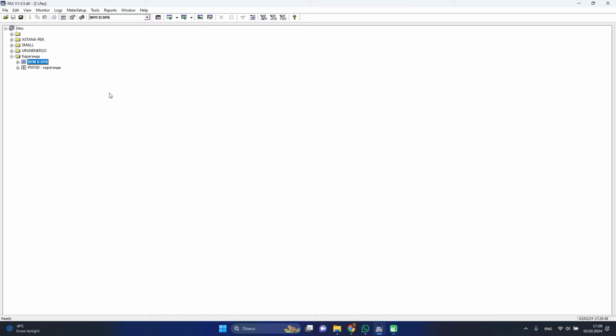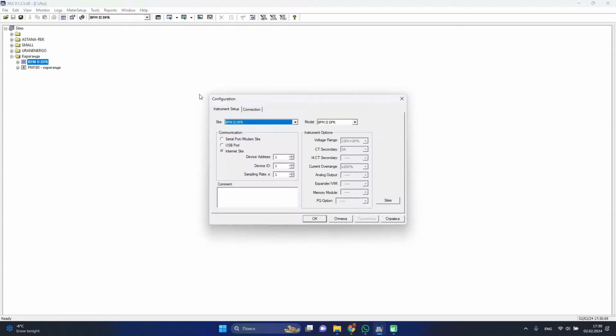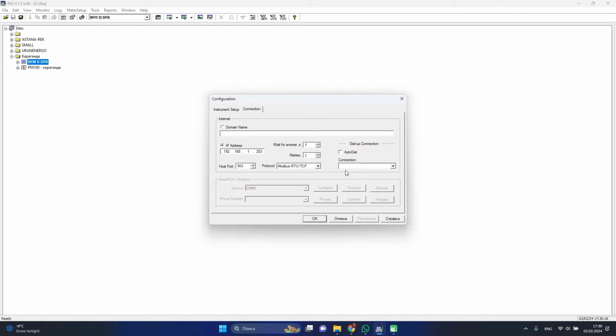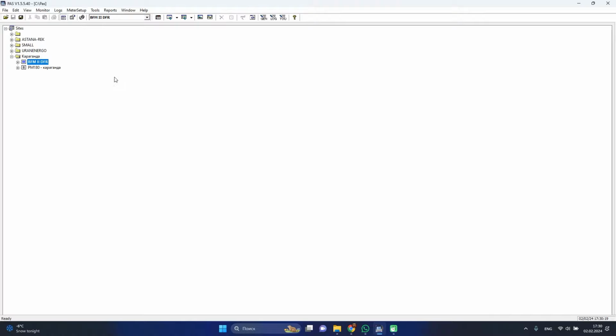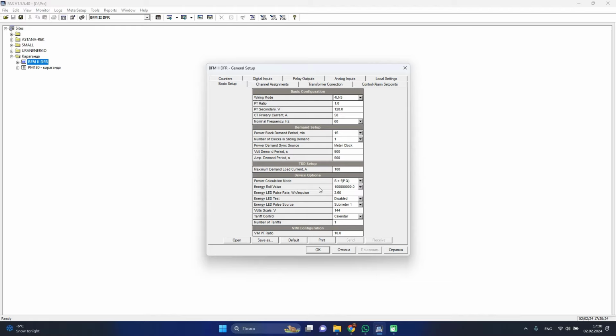Now let's have a look at how to configure the BFM II DFR in the PAS software. Here we have our site, and let's go to Tools, Configuration. Here we can select the device address, device ID, and model of our SATEC meter. After that, go to the general setup, and the main difference from the other SATEC devices is that we have a list of the submeters.